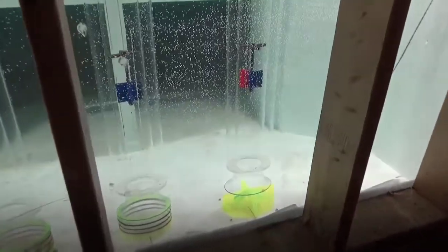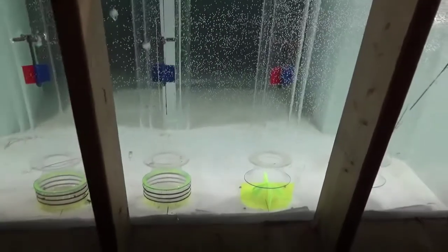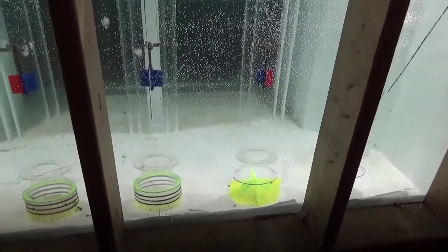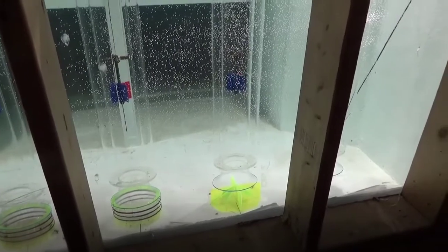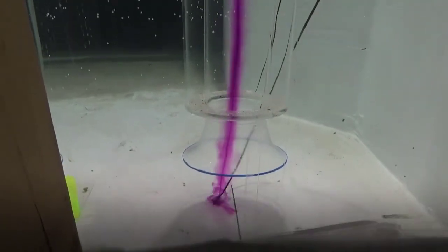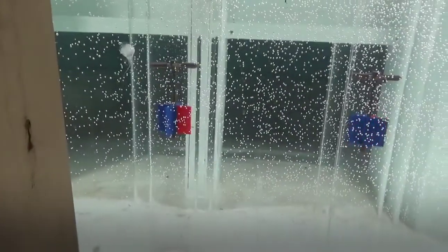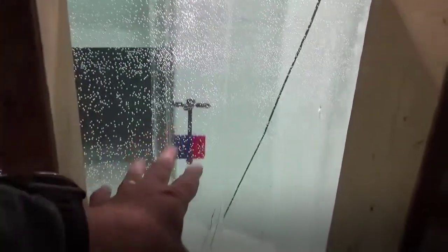All right, just one more test to show you here. We're at 17,670, so this would be 53,000 total with 3 pumps running. And notice your pre-swirl here again, and put some dye down there. You see that very strong floor vortex again here. No pre-swirl at all over on this pump right here. So we've got the same conditions at 15 all the way to 20 on our outer pumps, the 2 here and 2 here.